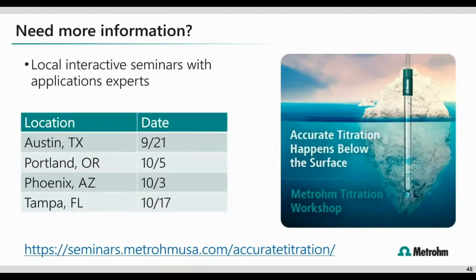When we look at the routine cleaning of exchanging that electrolyte, what we're doing is preventing the electrolyte concentration inside the chamber from increasing. If we begin to see it salt out, that means the electrolyte concentration inside is changing, and we need to keep that system as steady as possible. So keep an eye on those things once per week, and if you find that you can go every other week, that would also be appropriate.